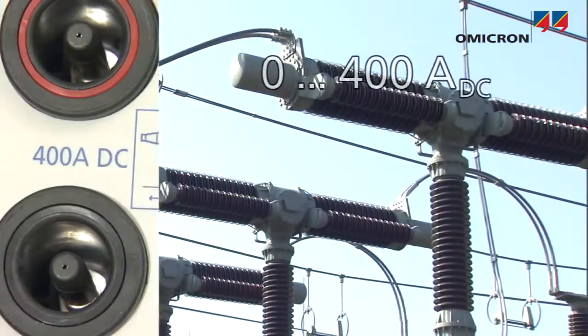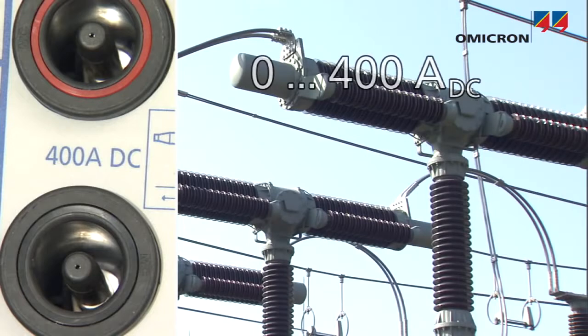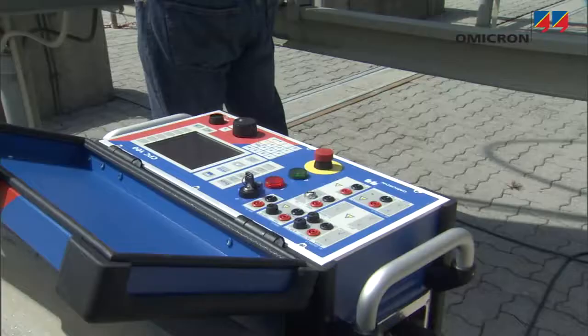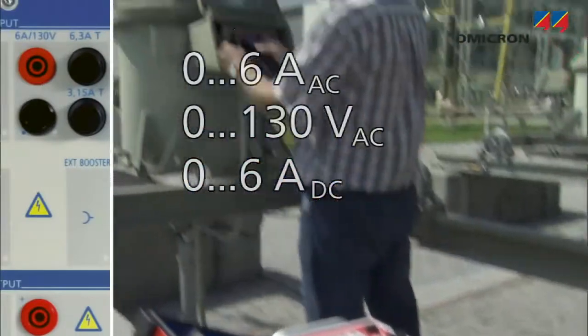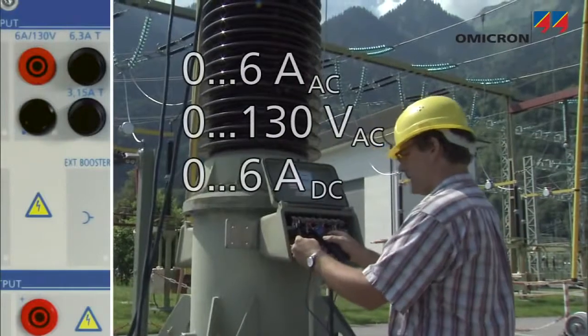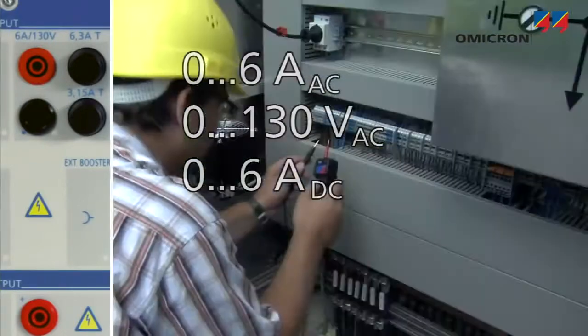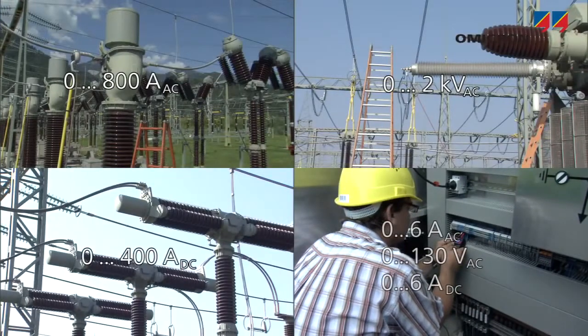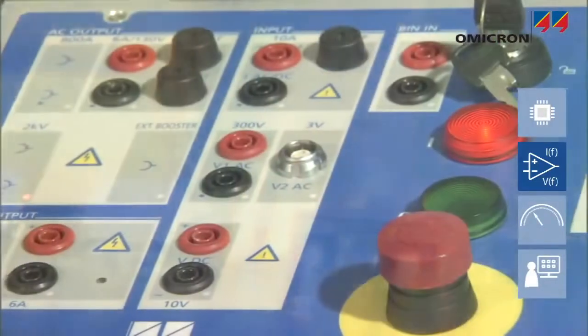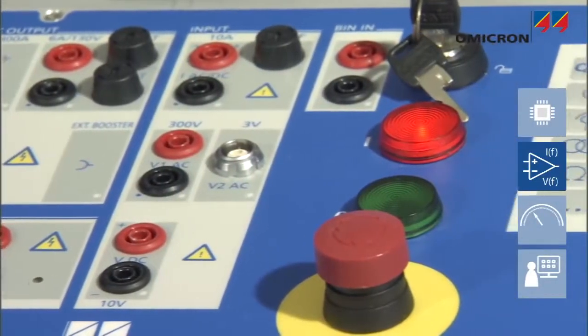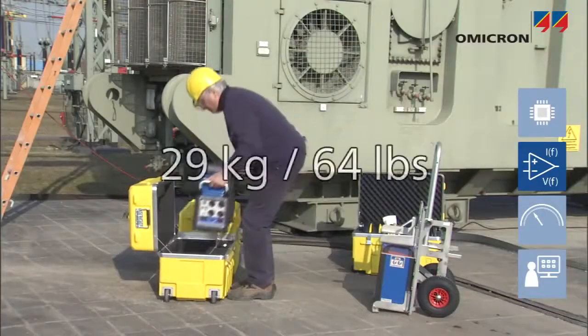The 400 amps DC output allows low resistance values such as contact resistance to be measured accurately. Small signal outputs are used for injection into secondary circuits, for instance, when measuring the burden or verifying the polarity. Using power electronics instead of copper and iron variacs allows combining all of these functions into a device that can be carried by one person.